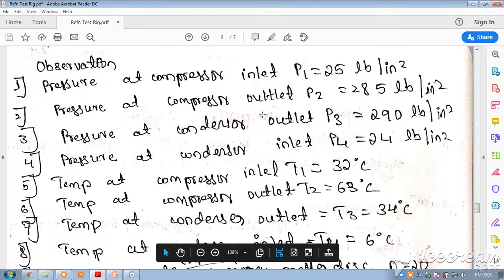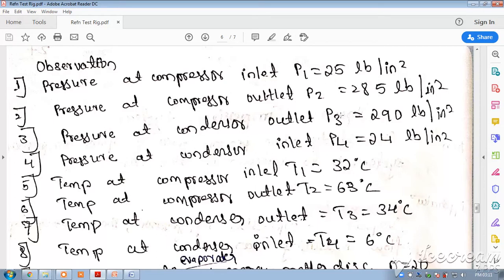The pressure at the compressor outlet and the condenser outlet are almost the same. As I told you, there are two pressures only: one is the evaporator pressure and the second is the condenser pressure. The evaporator pressure is the lower pressure and the condenser pressure is the higher pressure - that is 290 psi and here it is 25 psi.